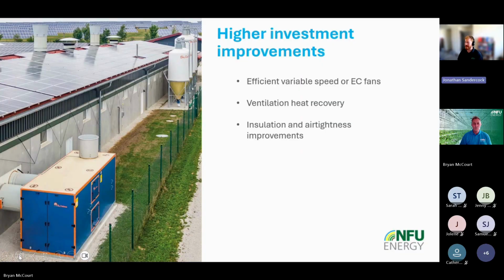So always trying to investigate what is the lowest energy consumption fan that can achieve your minimum ventilation requirements on the market for your particular use case. Variable speed ventilation can reduce electricity considerably, where fans spend substantial time operating below their full output. One commercial poultry study found variable speed control used approximately 25% less fan electricity than just purely on-off operation under its test conditions, although results will always vary based on your specific setups, so can't always promise that 25% improvement.